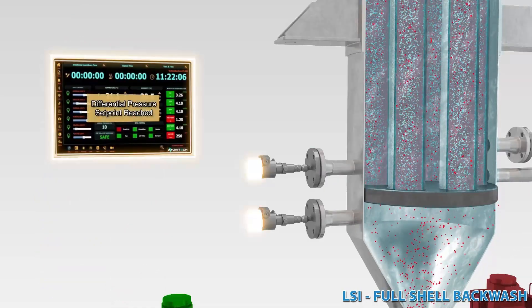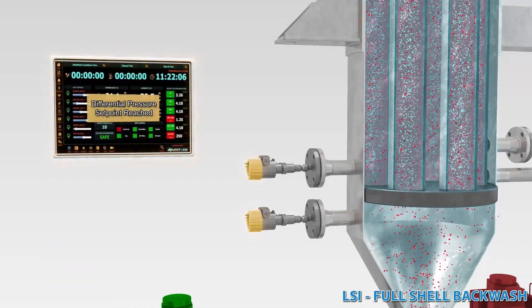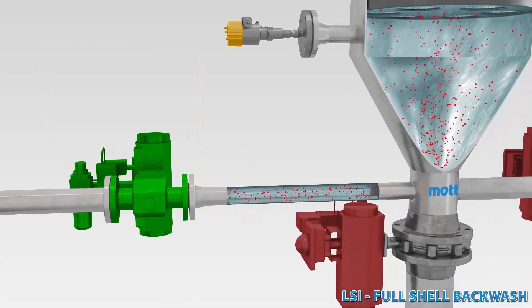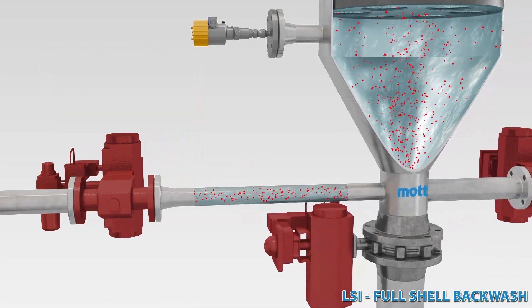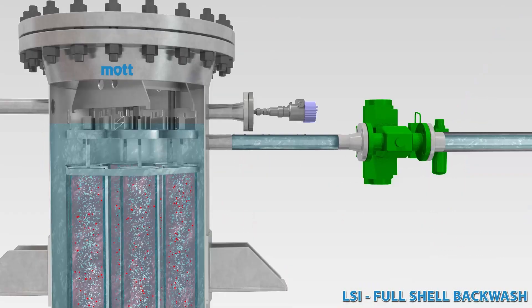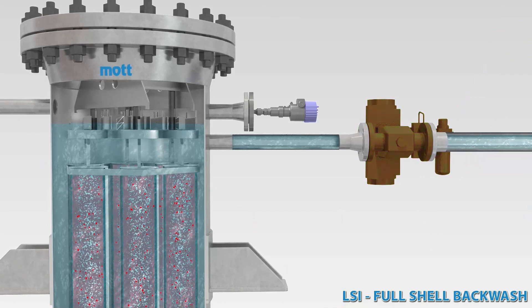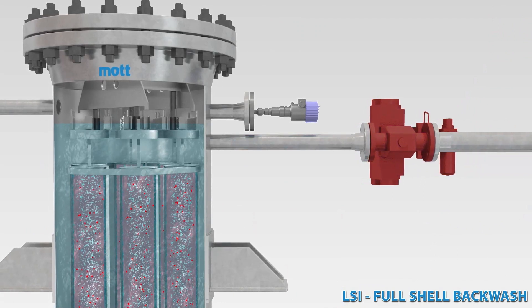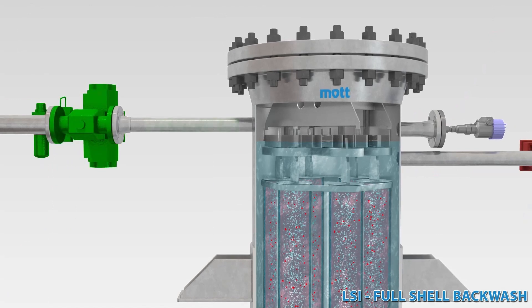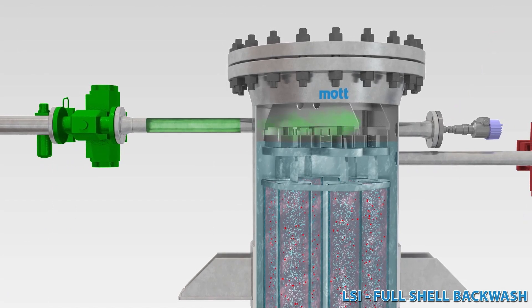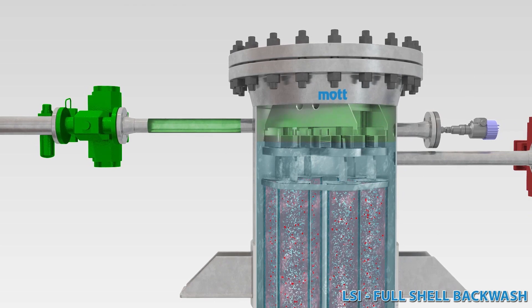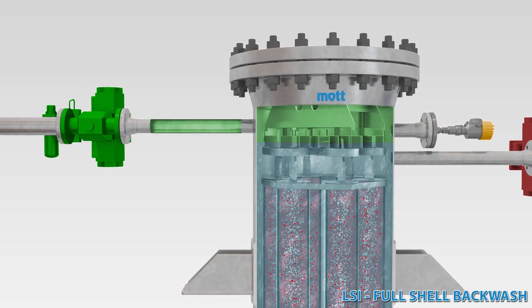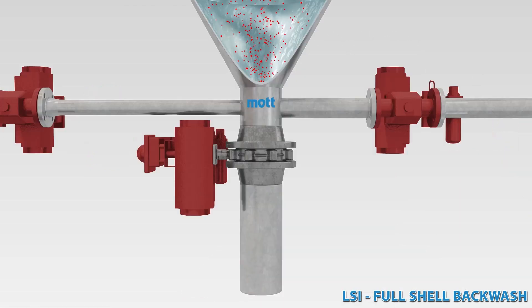When an LSI filter vessel calls for full-shell backwash, a signal is sent to the control system and the vessel is isolated from the process inlet and outlet. Pressurized clean gas is fed into the available gas pocket above the process filtrate. Nitrogen, air, fuel gas, or another available clean gas may be used.